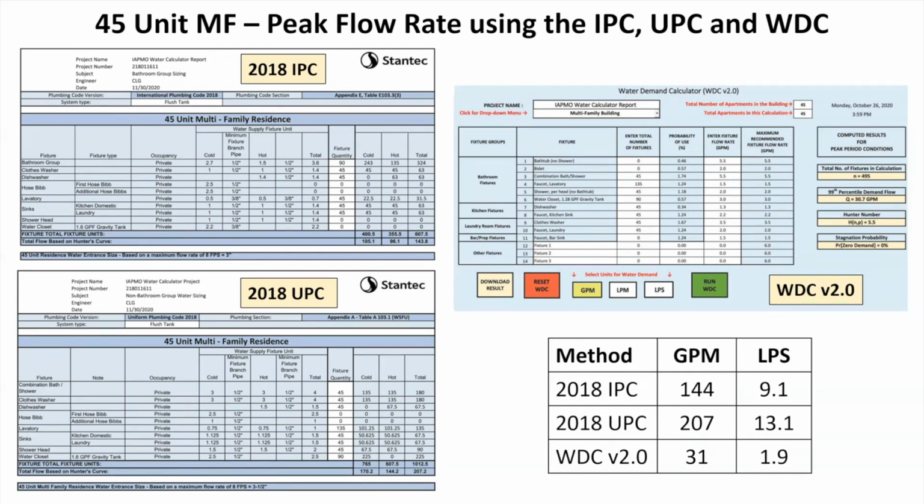Almost 7 times on the biggest difference. That's a huge difference in expected peak. And as Miriam pointed out, and Frank pointed out, if you've got measured data and you're not using it, we're fooling ourselves. We have huge extra volumes in the plumbing systems based on the current methods that are most commonly used here in the US.